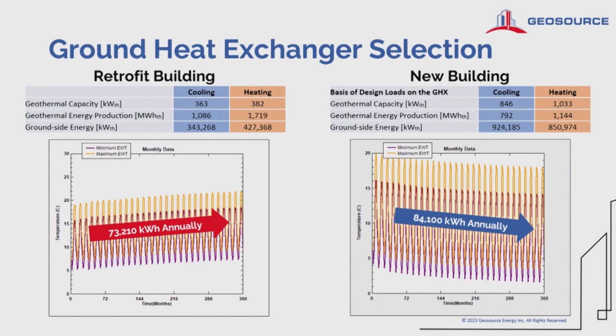When we evaluate the impact of building systems on ground heat exchangers, we utilize operational energy profiles. When investigating the retrofit building, we found that from the ground's perspective, the building profile was predicted to be cooling dominant. So this means that the building is going to be dumping more energy out of the building into the ground during the summer months to air condition the building. Then it will be pulling out of the ground in the winter to heat the building. The net result of this is an increase in ground temperature over time, which will eventually reduce system efficiency and potentially result in system failure.